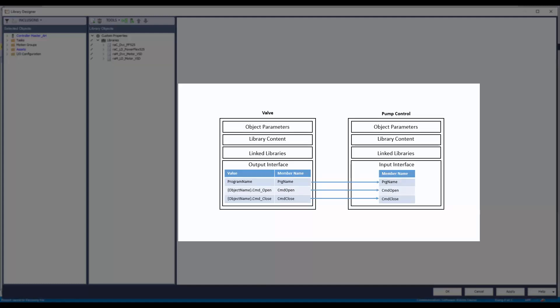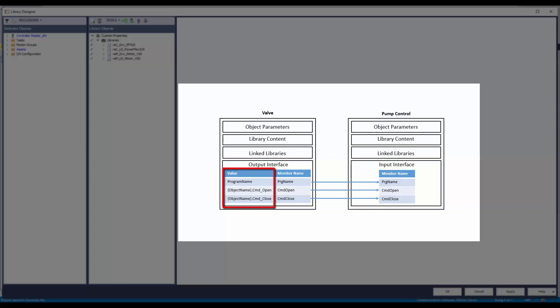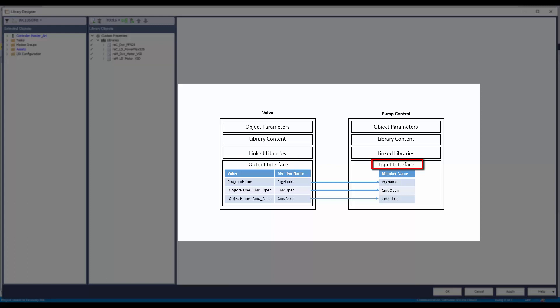A detailed explanation about interfaces: an interface is an object in a library that provides a link that another library object can consume. The link references an object in a library such as task, program, routine, or a tag. There are two types of interfaces: input and output. Output interfaces are connected to the input interface and allow variant tag member structures from different libraries to be mapped to a common interface member name. Input interfaces are used within a library without needing to know the provider's tag structure.